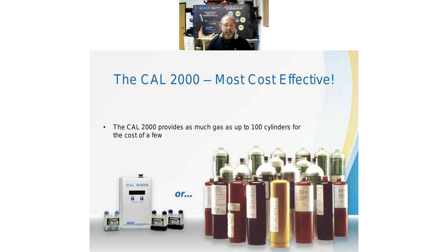So on cost effectiveness, you can imagine one of those little generating sources makes as much calibration gas as 100 cylinders. When you buy one of those cylinders of gas, you're buying usually 99.9995% air. And so you can see why one of those little generating sources can produce up to 100 hours or 100 cylinders equivalent worth of calibration gas. It's a very cost-effective and flexible way to make calibration gas.